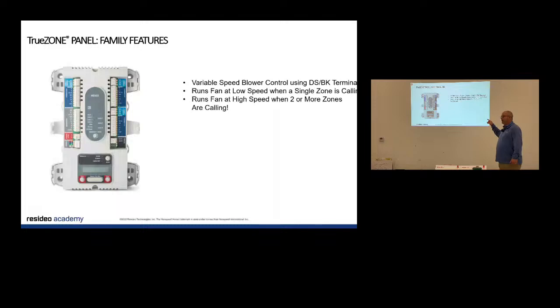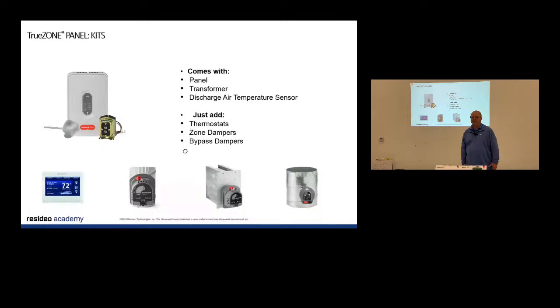If you went back to my nomenclature, a 322 is our most used panel. That doesn't necessarily mean you have to use it on 2-stage equipment. If you sold that to the guy, there's probably only about a $20 difference, and he had a single-stage piece of equipment, no problem. He just spent 20, 30 bucks more than he should have, but most distributors sell the 322 because the guy gets out there and has what he needs.